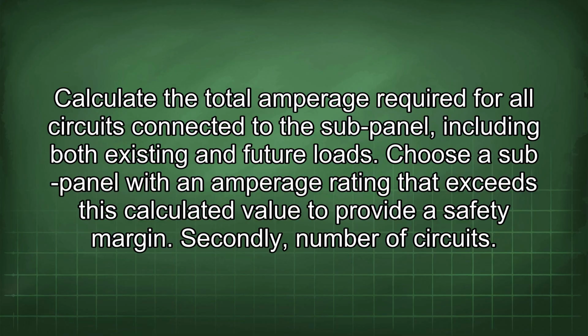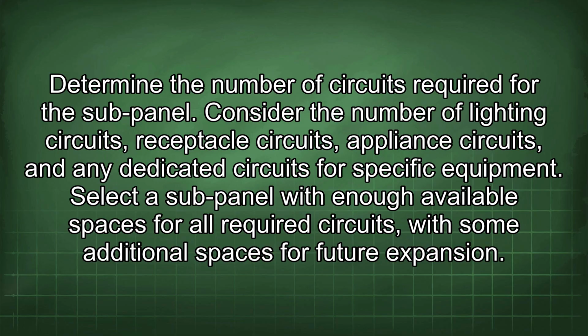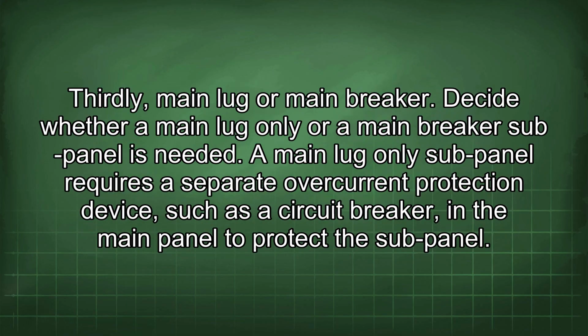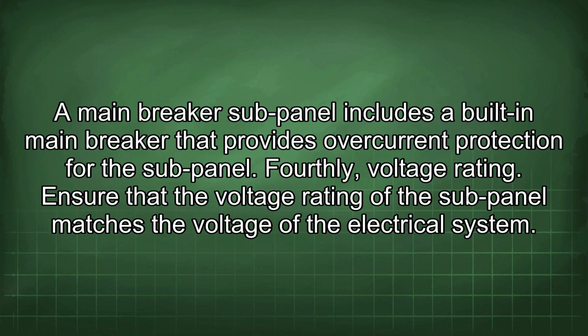Secondly, number of circuits. Determine the number of circuits required for the sub-panel. Consider the number of lighting circuits, receptacle circuits, appliance circuits, and any dedicated circuits for specific equipment. Select a sub-panel with enough available spaces for all required circuits, with some additional spaces for future expansion. Thirdly, main lug or main breaker. Decide whether a main lug only or a main breaker sub-panel is needed. A main lug only sub-panel requires a separate overcurrent protection device, such as a circuit breaker, in the main panel to protect the sub-panel. A main breaker sub-panel includes a built-in main breaker that provides overcurrent protection for the sub-panel.